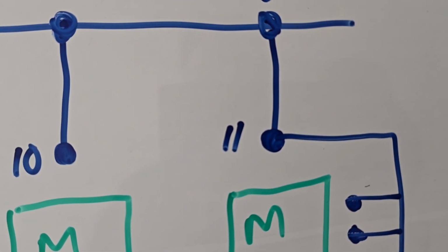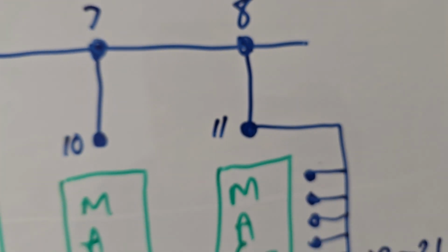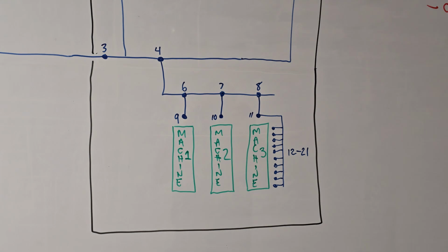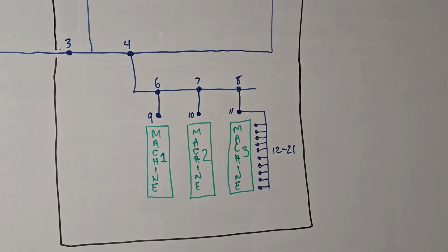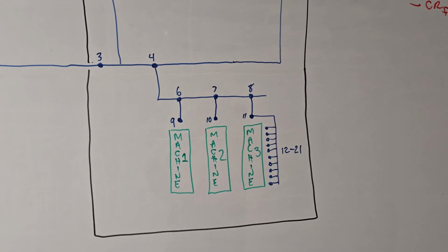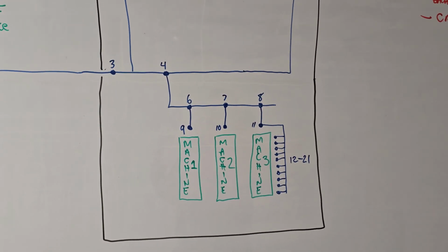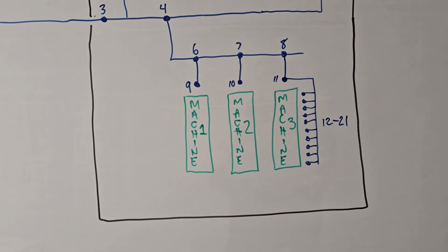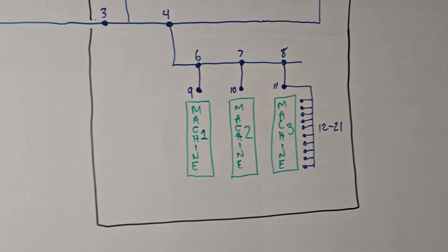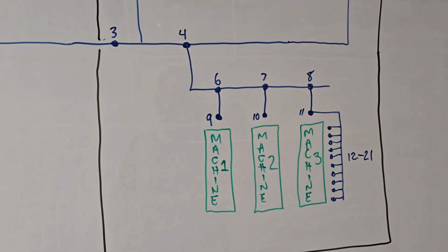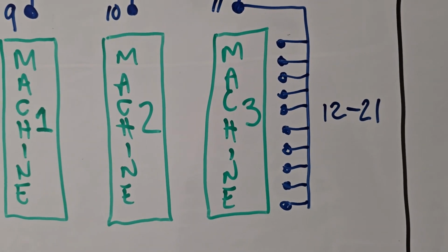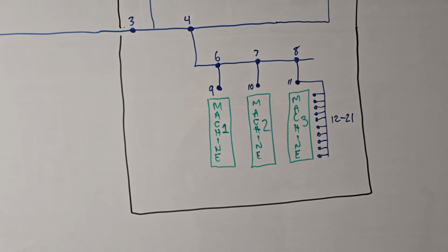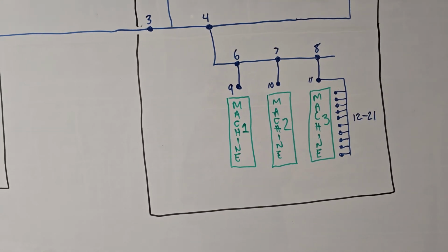There was data collection taken of pressure and flow at point 11. I want to say it was taken for a week or two, but they saw periods of pressure underneath 90 psi, 6 bar, which is what the set point is. The customer's specific problem is that this low pressure alarm is shutting down this machine, and they would like to know what the root of that problem is and how to prevent the shutdown of production.